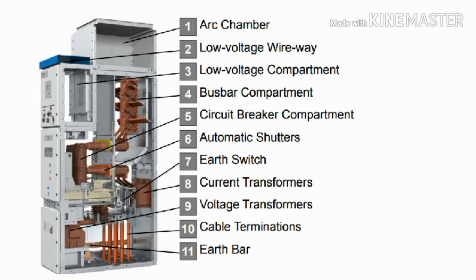Fourth is the bus bar compartment. On the back side of the switchgear panel is the bus bar compartment where the incoming supply of the switchgear is connected. Fifth, the circuit breaker is always placed in the middle of the switchgear panel. The bus bar and circuit breaker are connected so that from the top side of the panel the bus bar connects to the circuit breaker.